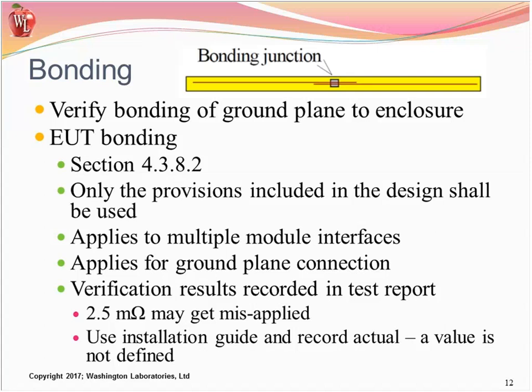4.3.8.2 says only the provisions included in the design shall be used. So what does that really mean to us? If I've got a rack of equipment that gets plugged in via an AC power cable, and that green wire is the only connection made, then that's the only connection that should be present during the test. And we know that a 2-meter power cable is going to be greater than 2.5 milliohms, so people applying this 2.5 milliohm requirement and forcing other grounds to be installed during the test are giving us fake answers.